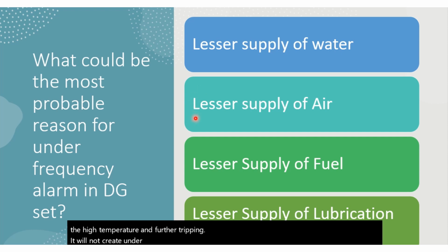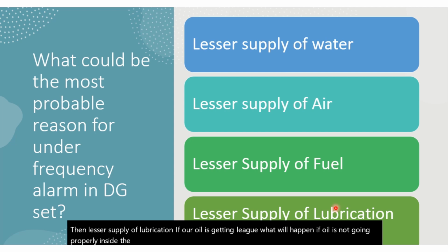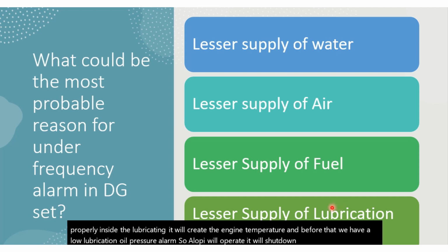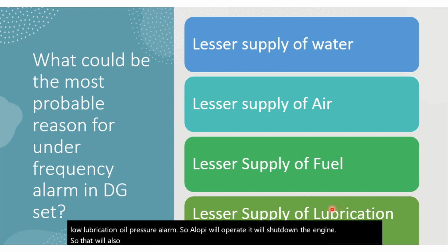If we give lesser air, if our air filter is jammed, what will happen? Insufficient air goes inside the DG set, because of which the fuel to air ratio will be disturbed and we might get black smoke. So this is also not a reason. Then lesser supply of lubrication. If our oil is leaking, what will happen? If oil is not going properly, it will raise the engine temperature, and before that we have a low lubrication oil pressure alarm. So LLOP will operate and shut down the engine. That will also not create under frequency.